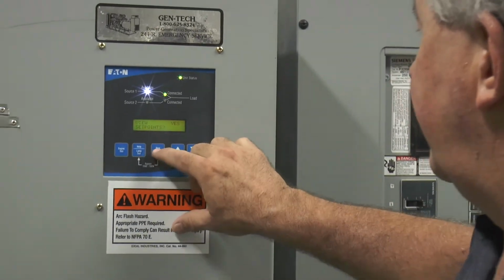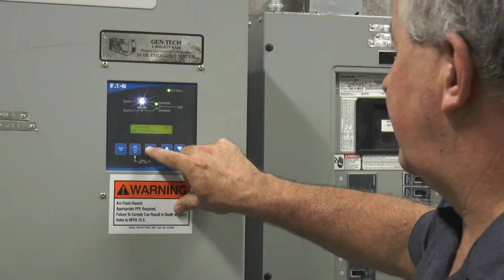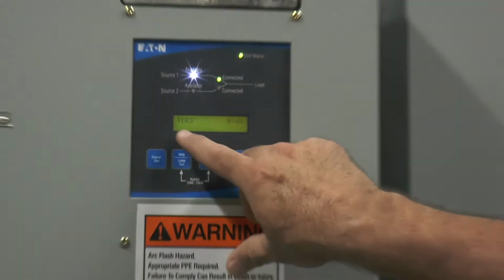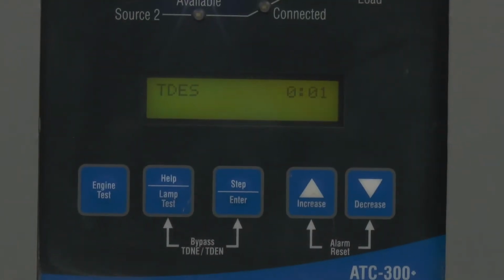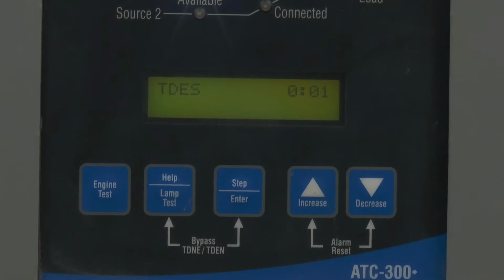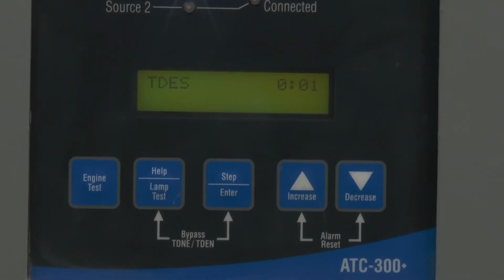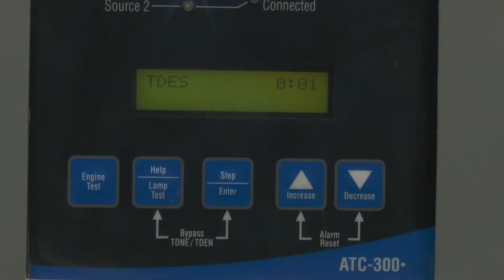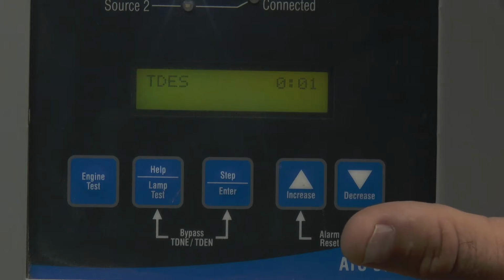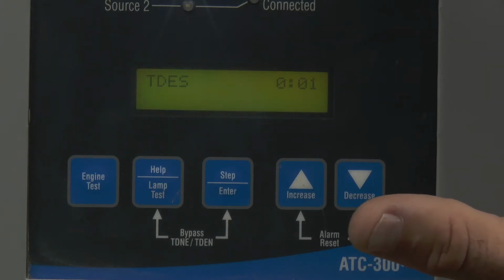So view set points, yes. Change set points, no. Time delay engine start: upon loss of utility power, 1 second will elapse before this transfer switch will give the start command for the generator to start. This switch by code has to be up and online in 10 seconds. The fire pump does too, but that's on a separate circuit.